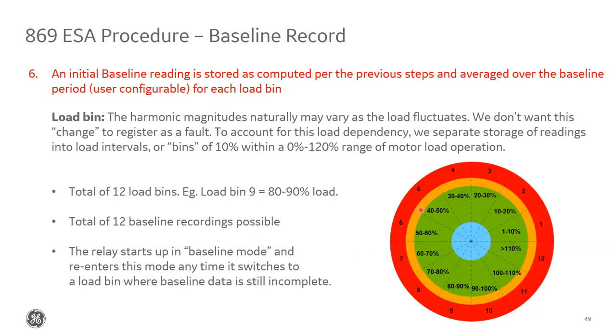And the recording doesn't need to be all at once. If the motor starts, stops, or sees a change in load, we'll dynamically switch between the load bin registers and record what we see in segments until the entire register is full. Once we see a total of the set baseline period recorded, then we'll switch into monitoring mode.